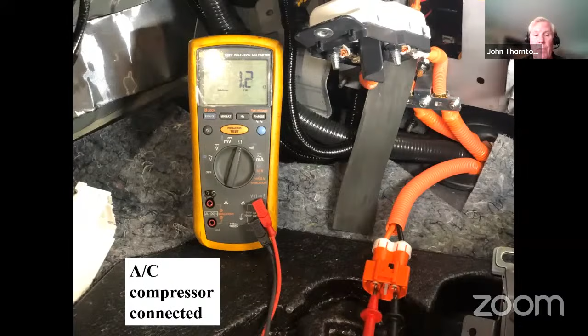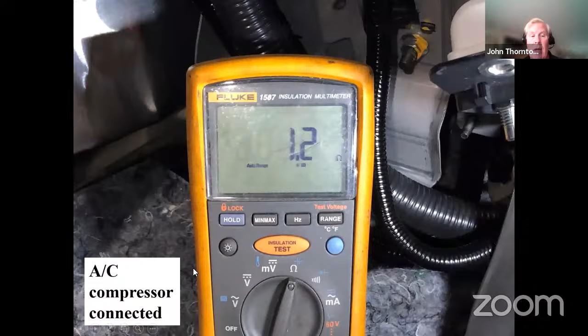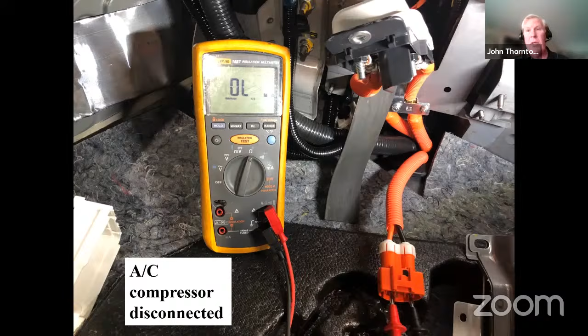Before we jump the gun, it's possible the issue could be the cabling shorted rather than the compressor. This picture shows my note here, that's with the compressor connected. Then we disconnected the compressor, fairly easy under the hood, and you can see the meter goes OL. This tells us it's not the cabling, it is indeed the compressor.